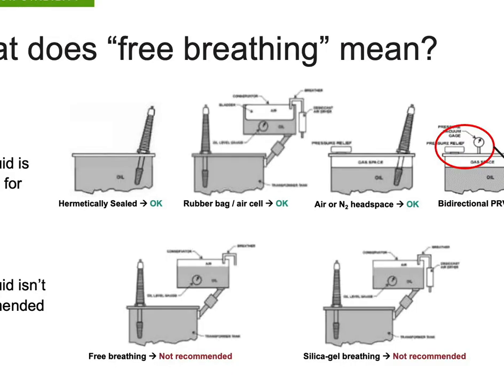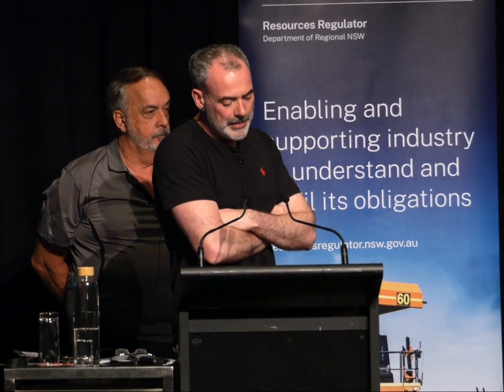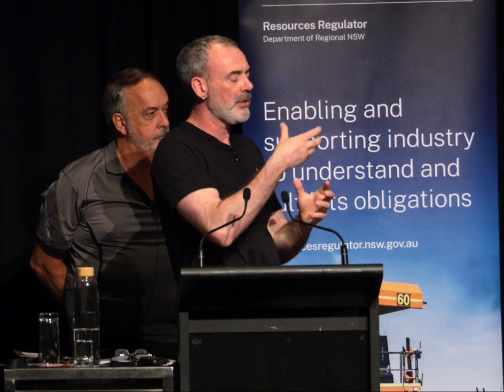So yeah, one of the considerations I mentioned for retrofilling was the free breathing status of the transformer. Many transformers are already sealed and they can be retrofilled, and if you look at the top of the page, there are some examples there. The hermetically sealed transformers; those transformers with a conservator and a silica gel breather with a bladder in the conservator. This bladder keeps the oxygen levels in the fluid low, so that's important. Also sealed transformers with a dry air or a nitrogen headspace. And another way to easily seal a transformer is just to attach a bidirectional pressure relief valve to the silica gel breather and reconnect. That's a low-cost way to seal a transformer.